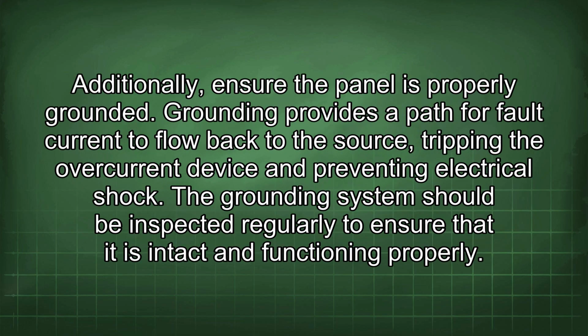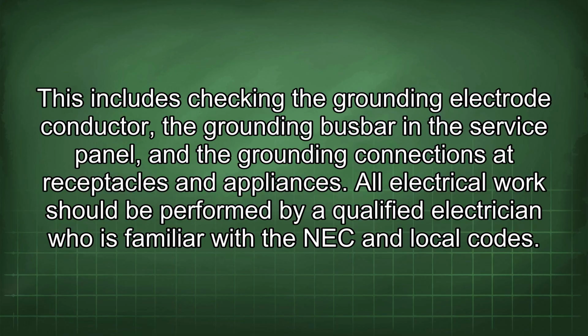Additionally, ensure the panel is properly grounded. Grounding provides a path for fault current to flow back to the source, tripping the overcurrent device and preventing electrical shock. The grounding system should be inspected regularly to ensure that it is intact and functioning properly. This includes checking the grounding electrode conductor, the grounding busbar in the service panel, and the grounding connections at receptacles and appliances. All electrical work should be performed by a qualified electrician who is familiar with the NEC and local code.